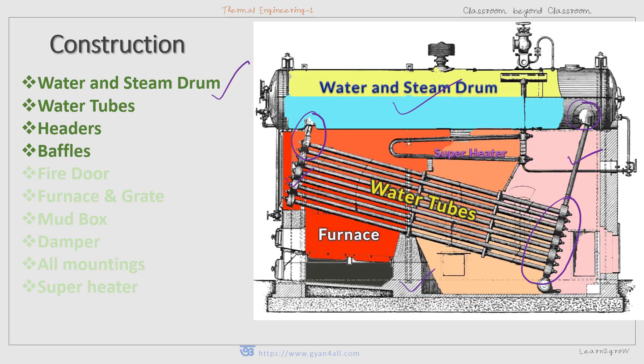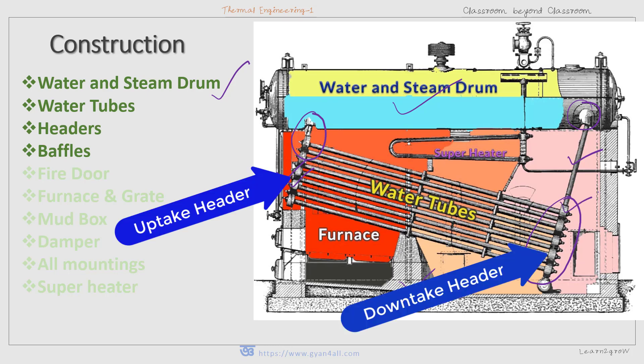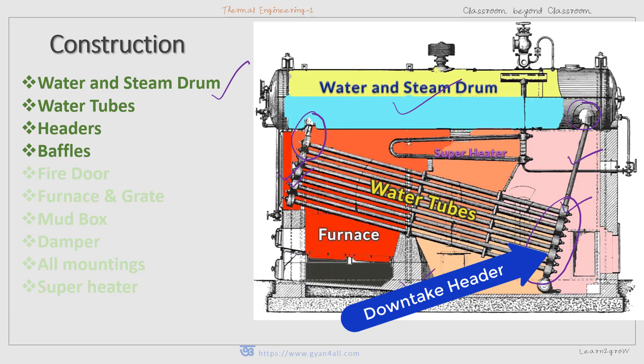Both the uptake header and downtake headers are connected by water tubes. These are tubes inclined at an angle of about 15 degrees to the horizontal, through which water passes and changes into steam. These tubes connect the uptake header to the downtake header.